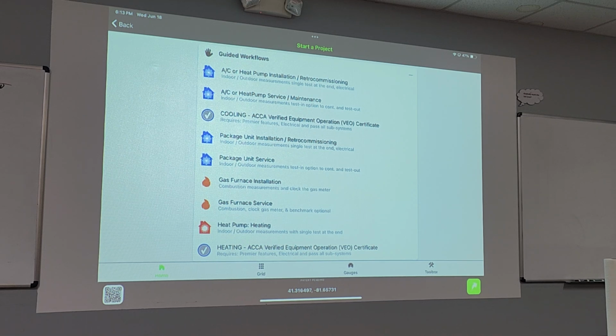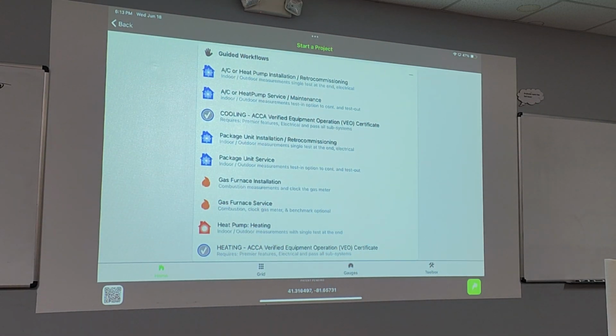Then it prompts you, you're able to generate a report - we call it our vitals report - where it's broken down into layman's terms as best we could, so that you can show it to a customer and say, hey, this is what we see, how do you want us to proceed from here? Make your repairs, then take your test out snapshot. This way the report will have a set of measurements on it before you make any repairs or adjustments, and then after. That's the difference between maintenance or service and installation or retro commissioning.